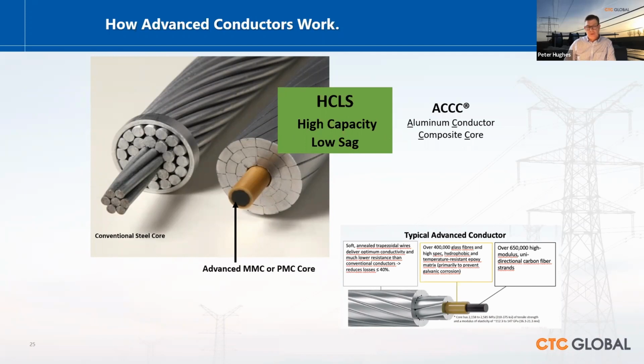As the composite core is much lighter than its steel core equivalent, we get over 20% extra conductive material for a given diameter, and you can see that clearly in the picture — there's much more fill. That's really the high capacity part of this technology. By high capacity, we also mean lower resistive losses per kilometer, or lower operating temperatures for the same current. It's better to have more capacity at the same or lower temperature, which means less generation.